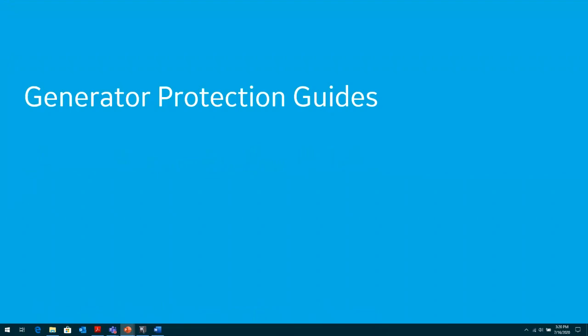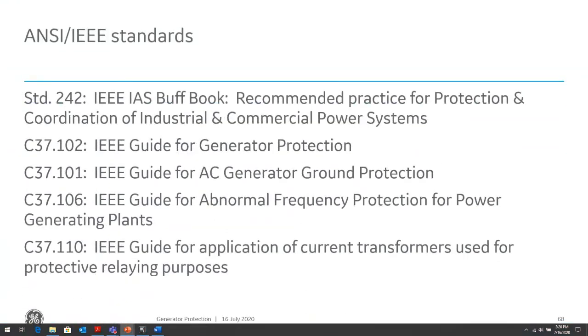The generator protection guidelines are what we can refer to when we determine what type of generator protection to use, and a lot of the things I've talked about come from these guidelines. There are some things I didn't talk about, like injection for stator ground faults and some other techniques, which are not applicable so much to industrial but more to the utility side. We're talking more on the industrial side. You can look at these guides to see some additional techniques, including subharmonic injection to determine ground fault currents within generators, and high impedance grounded generators.